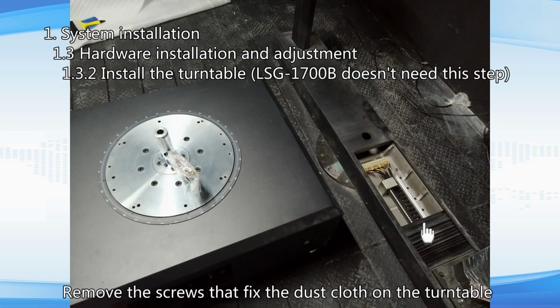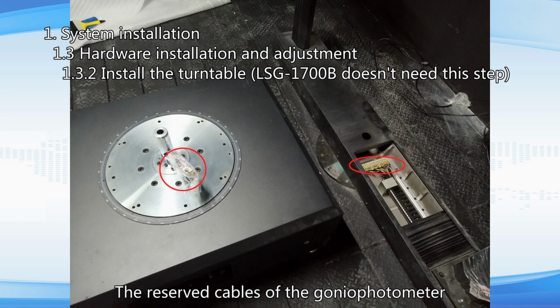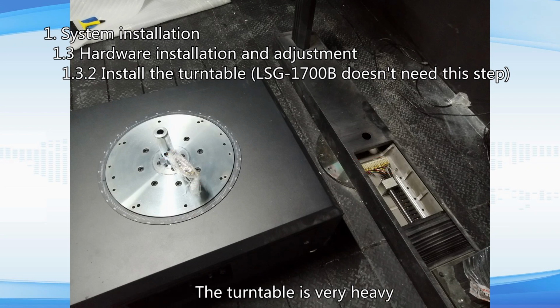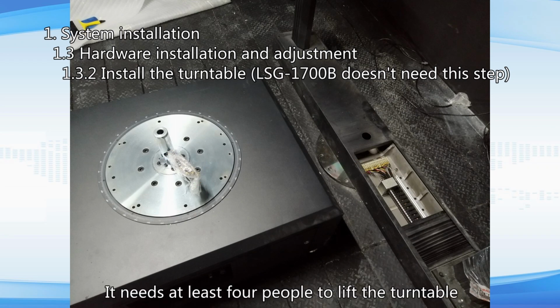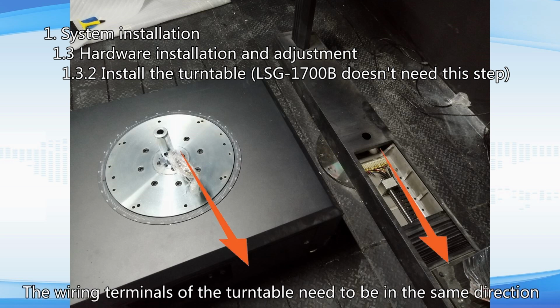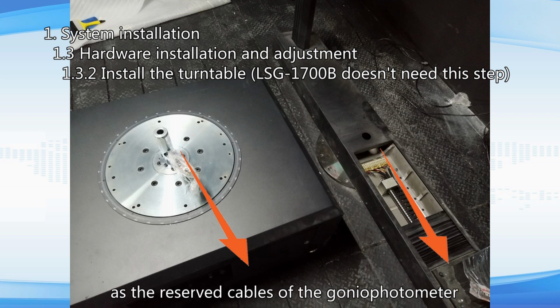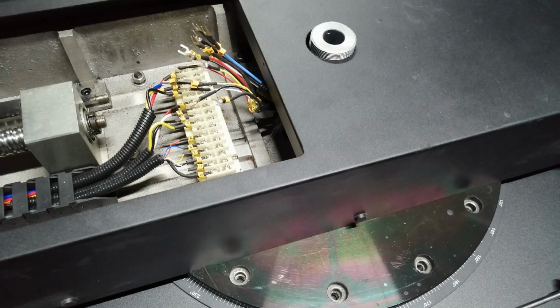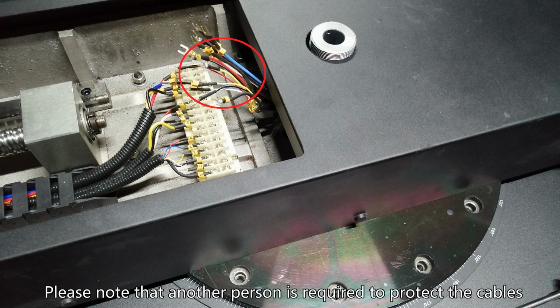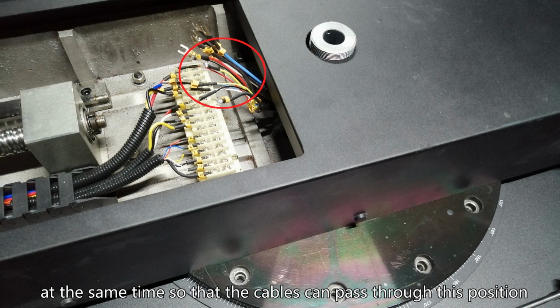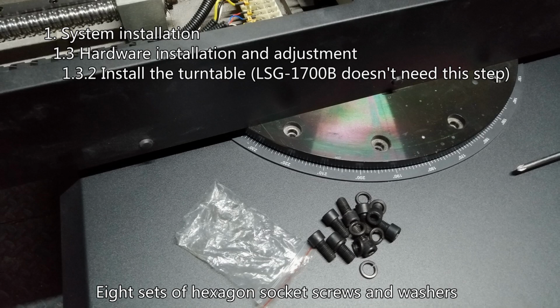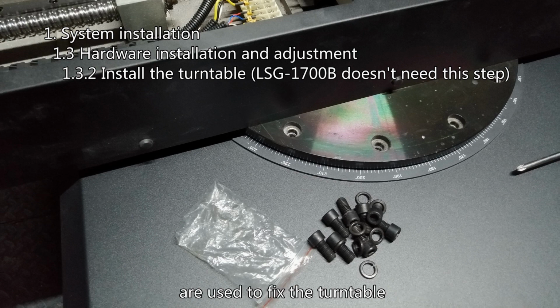Remove the screws that fix the dust cloth on the turntable. The reserved cables of the goniophotometer need to be connected to the turntable. The turntable is very heavy. It needs at least 4 people to lift the turntable. The wiring terminals of the turntable need to be in the same direction as the reserved cables of the goniophotometer, and place the turntable on the base. Please note that another person is required to protect the cables at the same time so that the cables can pass through this position. 8 sets of hexagon socket screws and washers are used to fix the turntable.